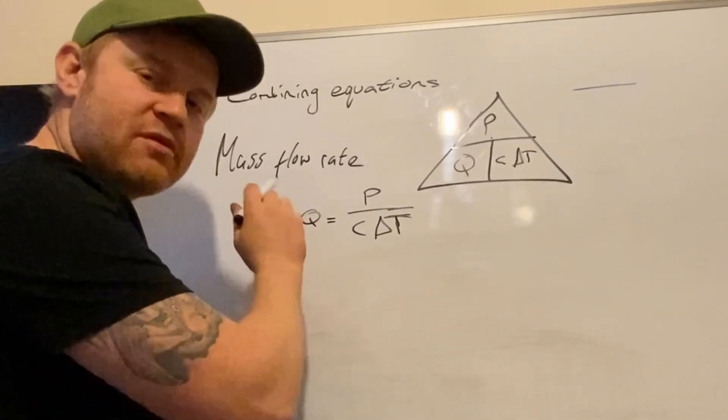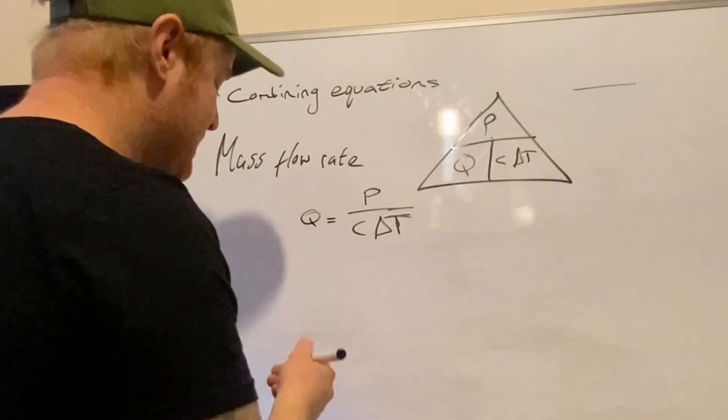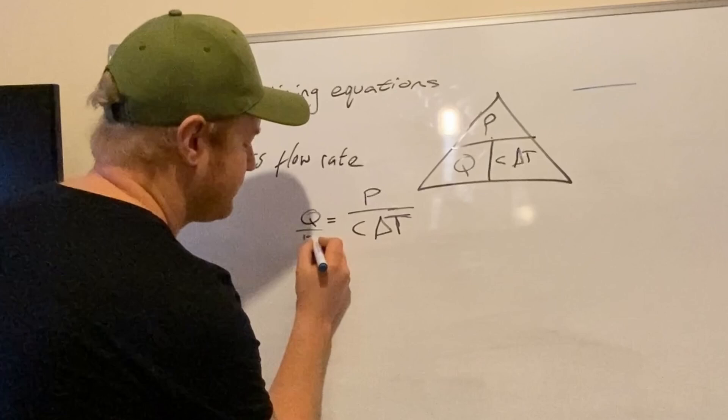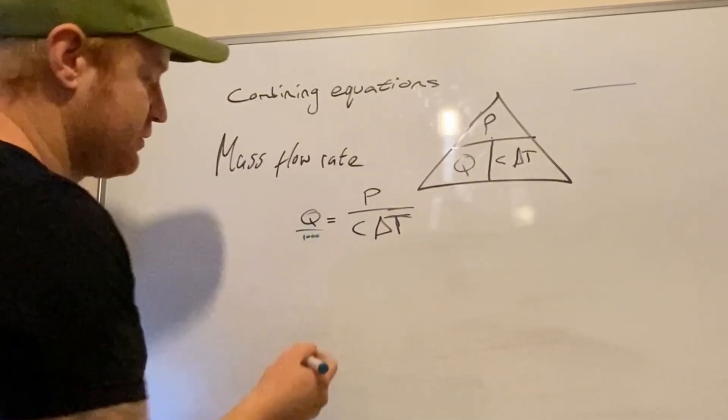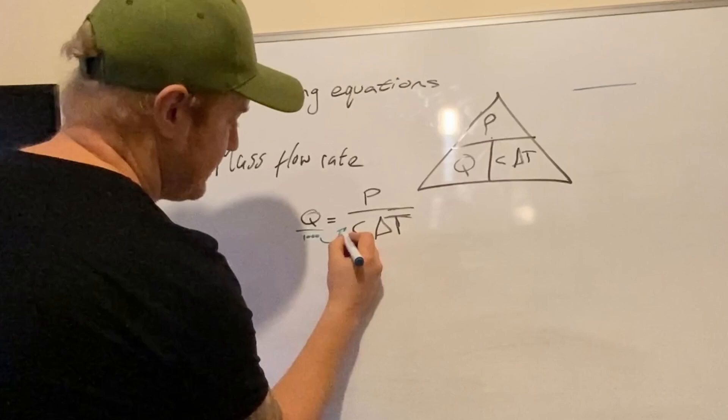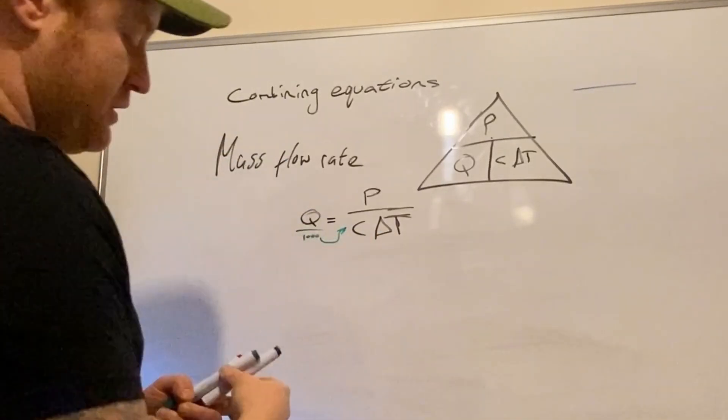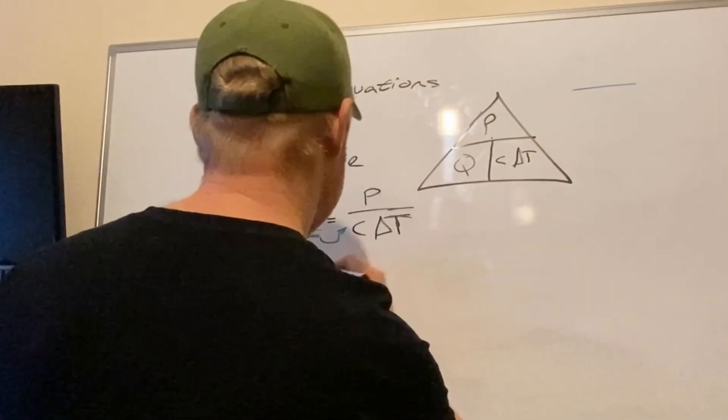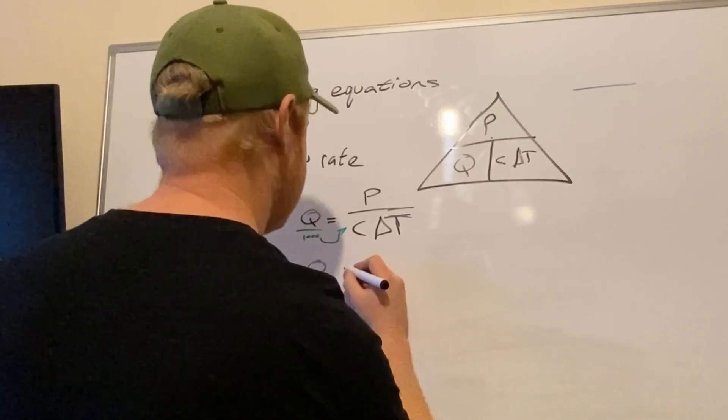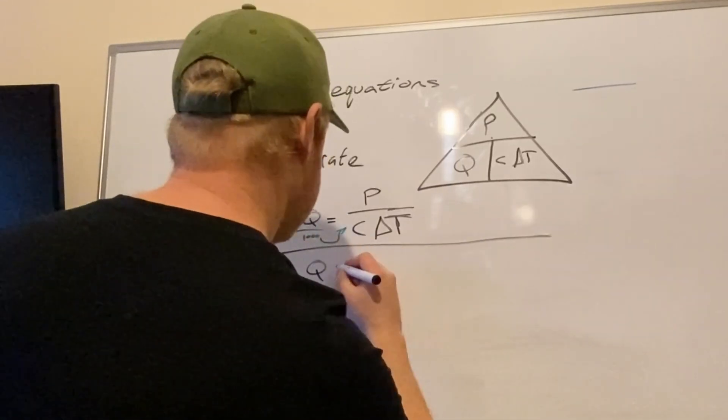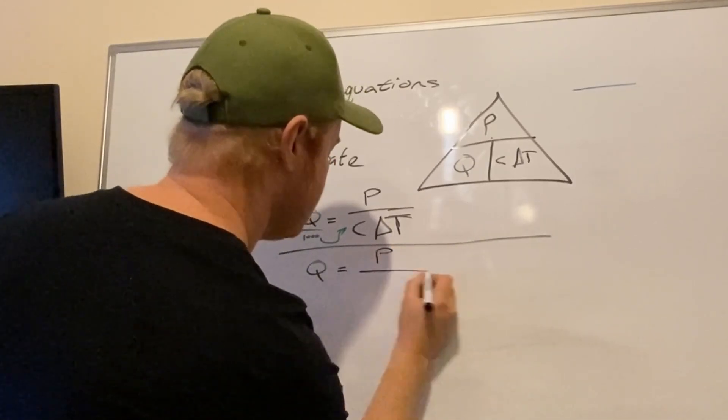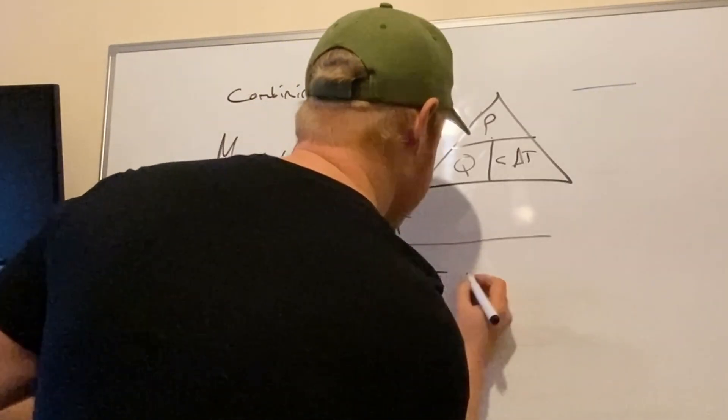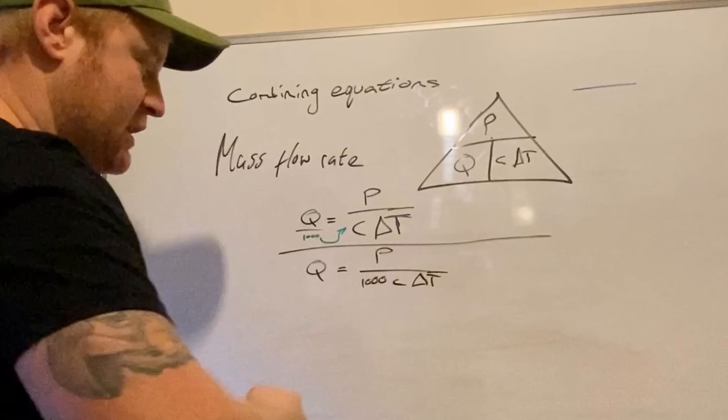However, when we use this in our pipe sizing calculation, we use meters cubed per second, which actually is liters per second divided by 1000. So what we want to do is put this here. So to get flow in meters cubed per second, we go: q equals power divided by 1000 times specific heat capacity times delta T. So there's your meters cubed per second. That's your mass flow rate equation.